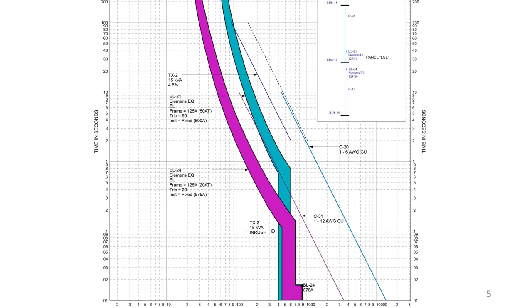And the biggest issue is that a 15 kVA transformer is so small, the available fault current is very low. It will take a very long time for these breakers to react and trip in the event of a fault. And there's no way you can achieve selective coordination between a 50 amp circuit breaker and a 20, even if this would have been a 100 amp circuit breaker, which is like a 5-to-1, you would still not get selectivity. Therefore, our recommendation was to replace the 50 amp device with a fuse, and the customer had to spend extra money in doing that.